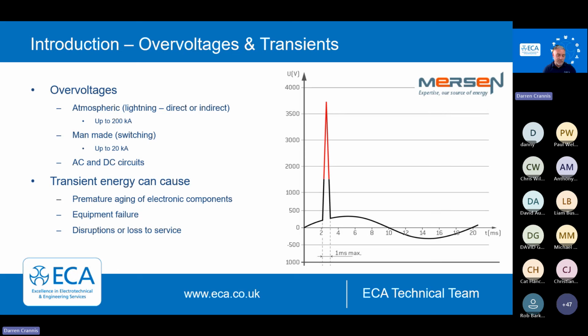Where we're interested in BS 7671 predominantly is Type 2s. It's the man-made switching. And that's typically all indirect strokes, so lightning hitting elsewhere and that transient coming into our networks. 20 kA is typically the value for those ones, most are around the lower region of 5. You've got to remember, you see here there's a voltage spike, and we'll come on to that in a moment, but it's a colossal amount of energy we're dealing with, and that may lead to premature aging of electronic components, equipment failure, and can cause disruption and financial loss.